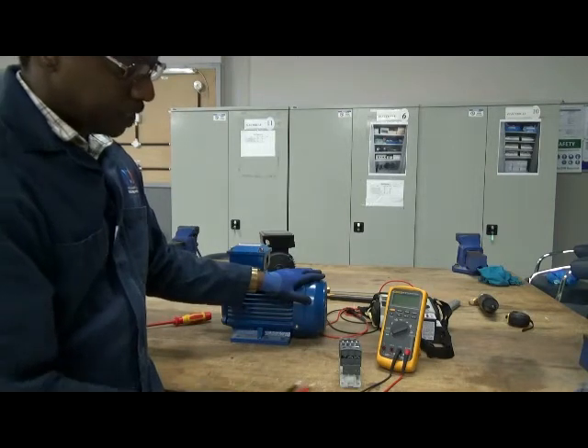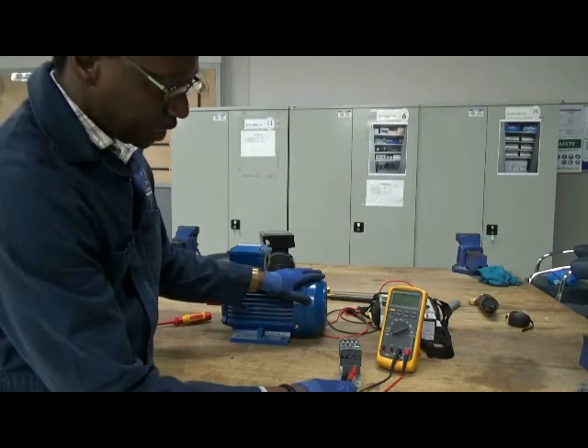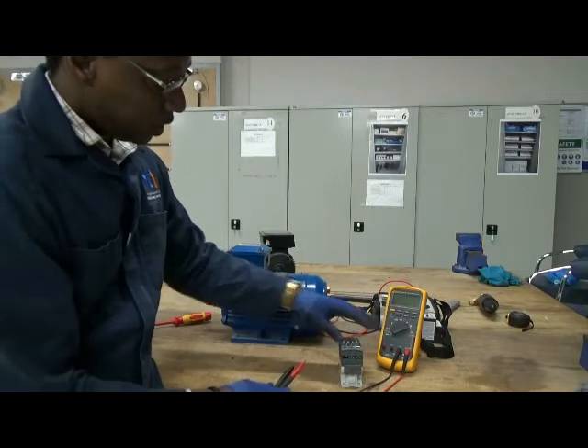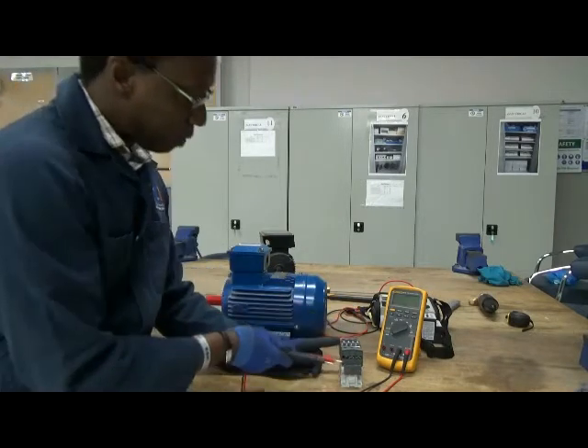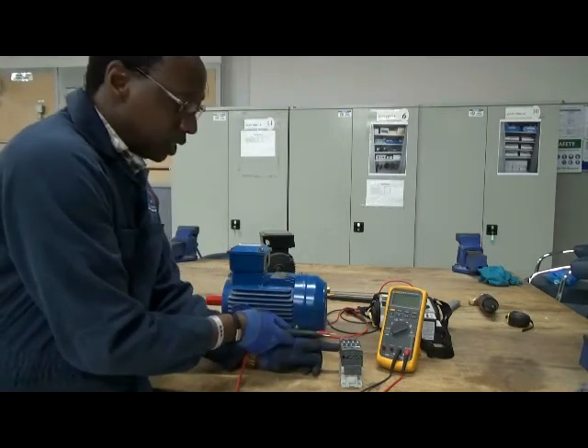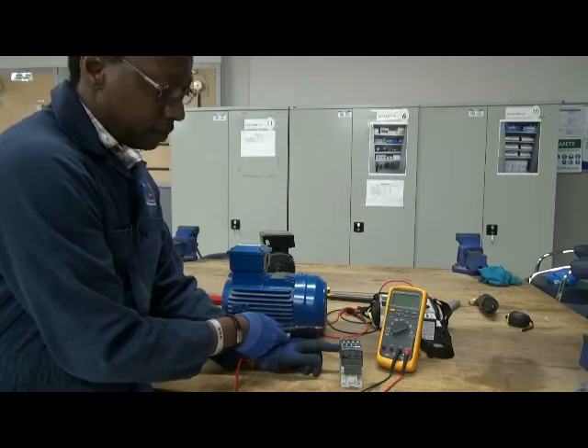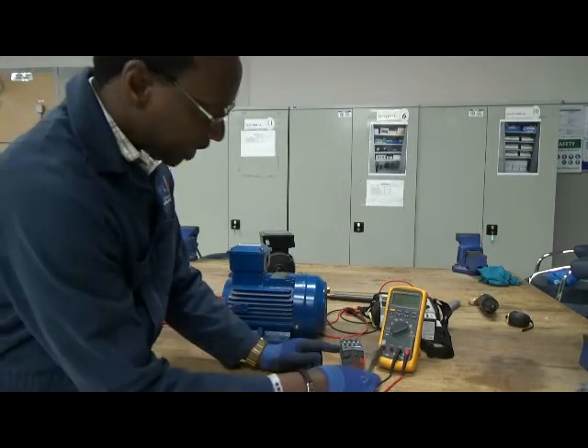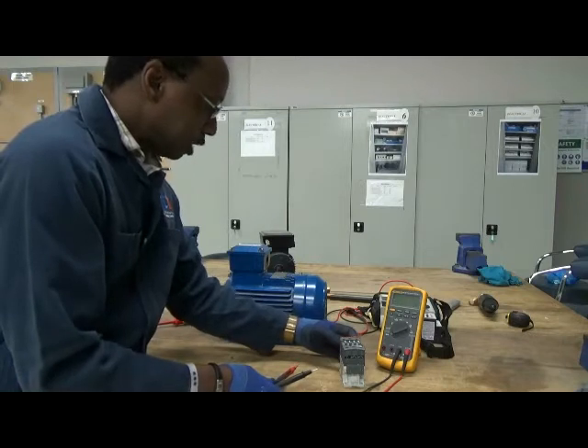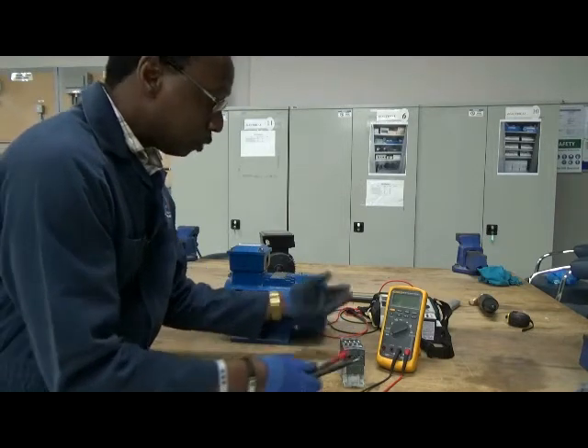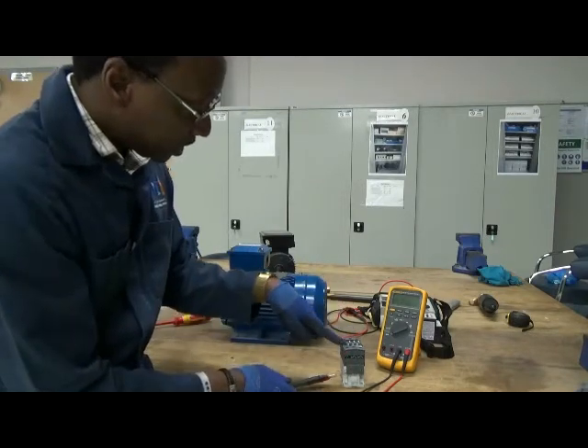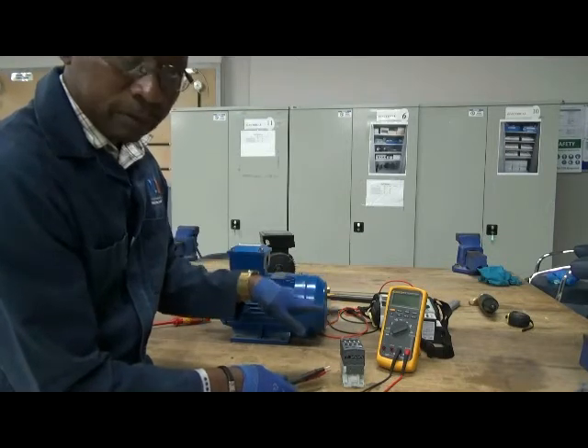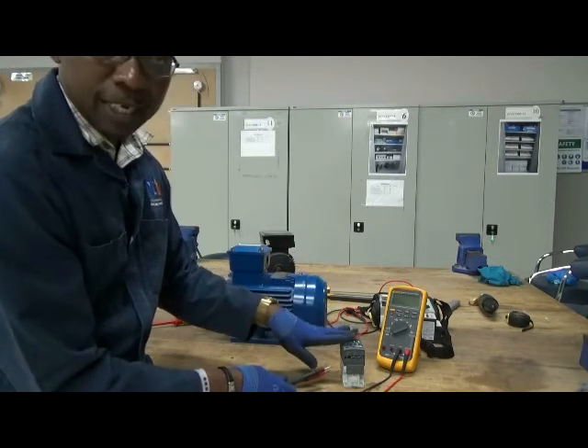So what is going to happen is if I connect my supply to the coil, the three main contacts will close and the power will be able to pass through the contactor. Because right at the moment, if I've got power coming in and 3 wires going out, power will not be able to go out because at the moment the contacts are open. The contacts are open inside.